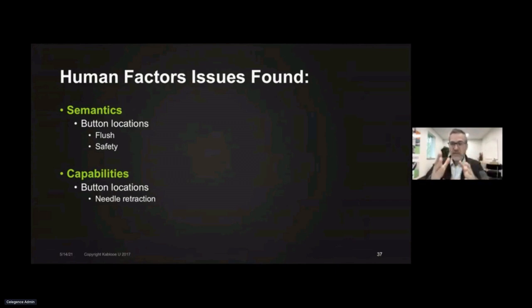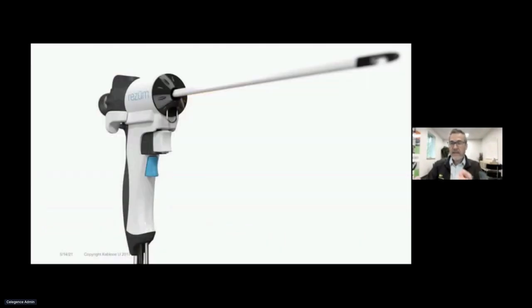These pain points turn into user needs, and we write them up as user needs, which then go into our requirements document as user requirements. And these become design inputs for our DVT testing. So these are inputs into our design controls, but they're usability ones.